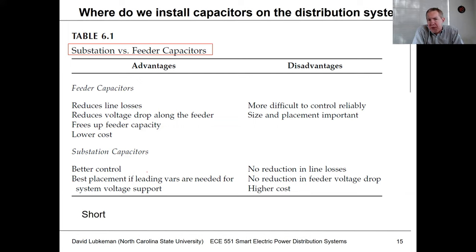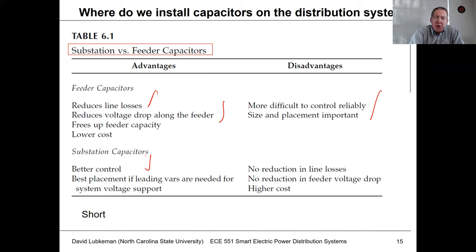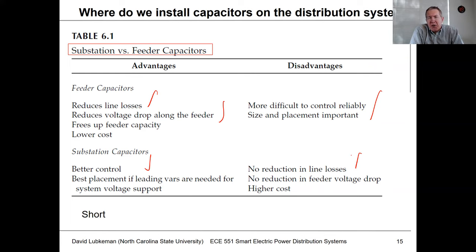As a distribution planner, capacitors can be placed either out in the feeder or at the substation. Placing them in the feeder gives more benefits for loss reduction and feeder voltage improvement, but requires communications to a device in the middle of nowhere. Placing them at the substation offers more convenience for substation automation integration but doesn't provide in-line loss benefits. If all you need is to minimize VARs from transmission, the substation may be the best bet. In practice, utilities use a combination of both.